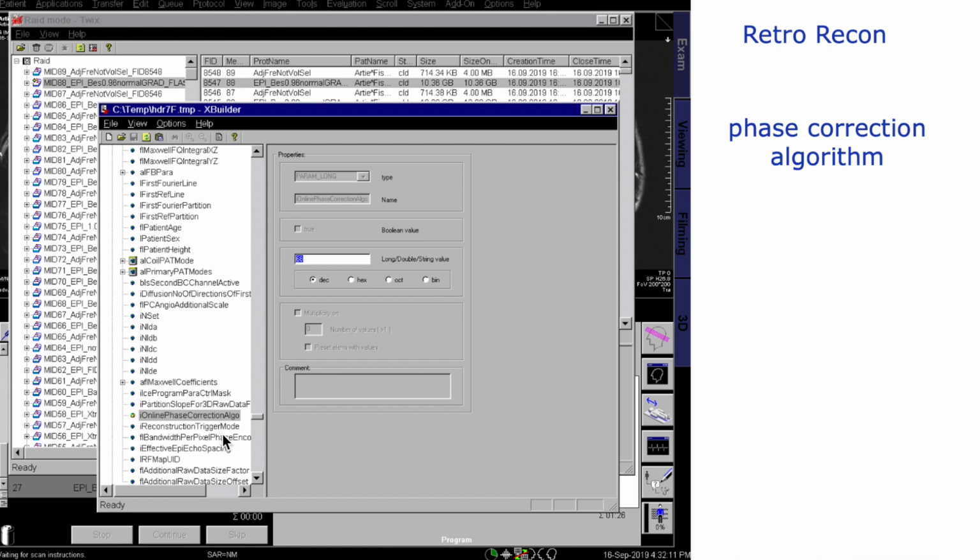This refers to a Nyquist ghost correction in EPI that we will manipulate in the next step. And this is a parameter that only applies to EPI. Therefore, it is not included in the EVP ICE config file, but it is definitely included here. And here the default parameter would be 68. So for now, let's not change it, but just reconstruct it again.